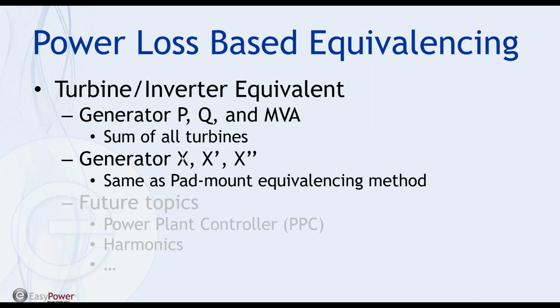Same story applies to generators. For the synchronous impedance, transient impedance, and subtransient impedance, I can do the same thing. I don't have to change the per unit quantity, but just raise the generator MVA base to n times the single generator MVA base. Then I got my equivalent, because if you have multiple generators connected in parallel, it's the same thing, right? And the total amount of active power, reactive power, and apparent power would be the sum of all turbines. That's it. Theory-wise, it's pretty straightforward and simple.